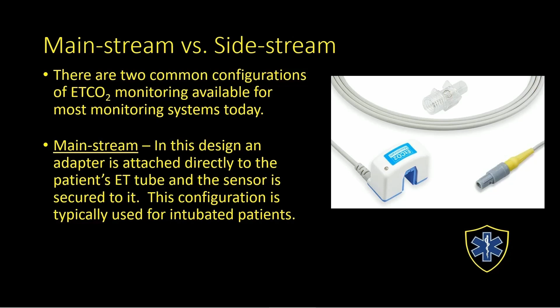So, what could we do to have our sensor a little bit more protected and a little bit safer? Also, another limitation we have on this is it's only for intubated patients, so it kind of limits what we can use it for. Let's look at another configuration. This is the side stream configuration. Now, in the side stream configuration, this connects to the cardiac monitor. You'll notice the connection is very similar to the one before. And in that low flow case, which is very well protected and hardened, there's actually a pump.